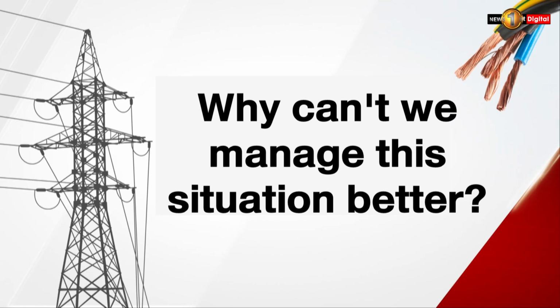Why can't we manage this situation better? Solar power plants operate by supplying electricity to the grid. When we look at the system, we see that the actual demand is very low. During periods of low demand, we have to generate a minimal amount of electricity. For example, during yesterday's incident, Norochcholai typically supplies around 810 megawatts, but we had to reduce it to about 450 megawatts because the actual demand was even lower. The visible demand on the system was lower than the actual electricity consumption because solar power plants were supplying part of the demand. However, when the system's load drops to around 800 megawatts, its stability decreases.